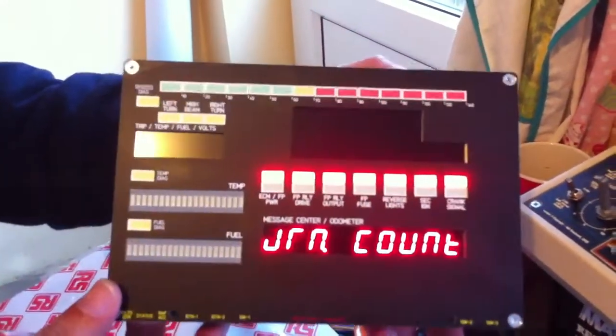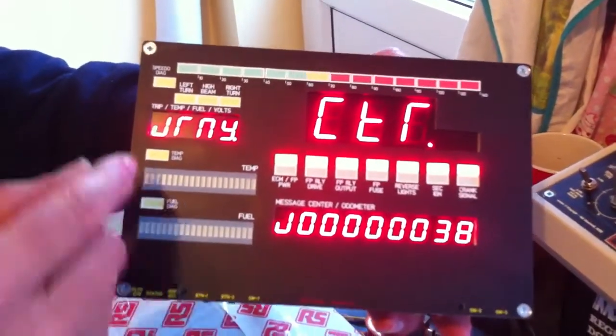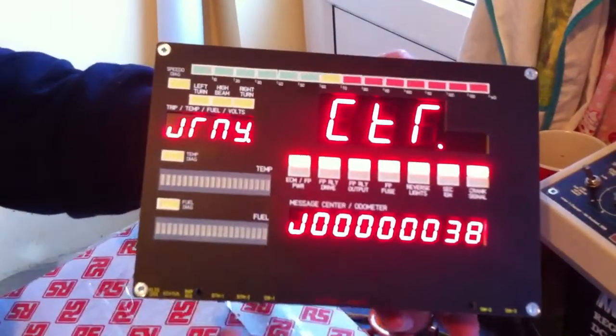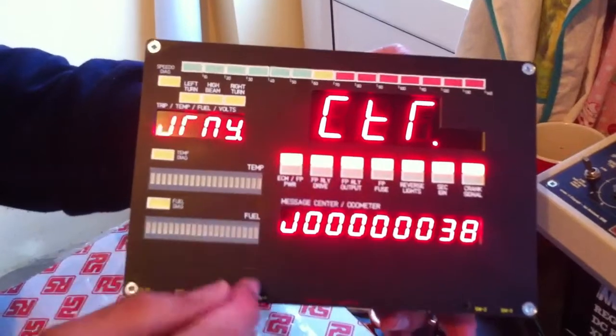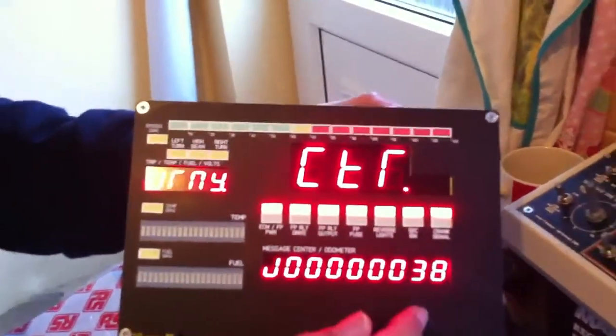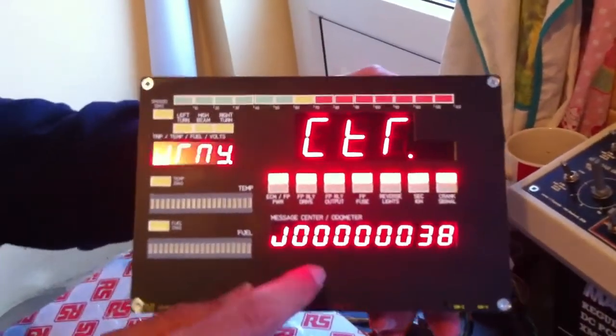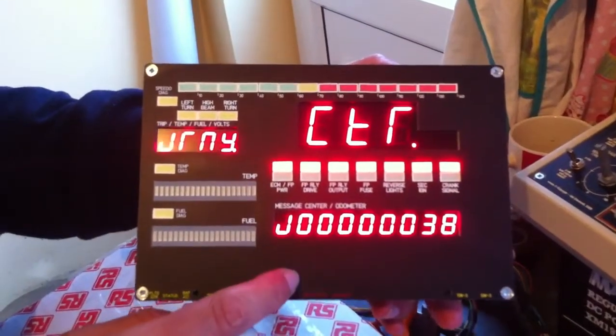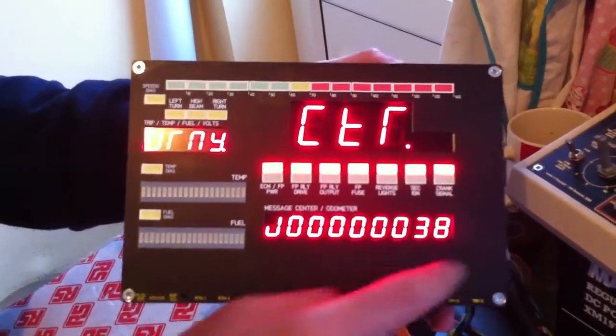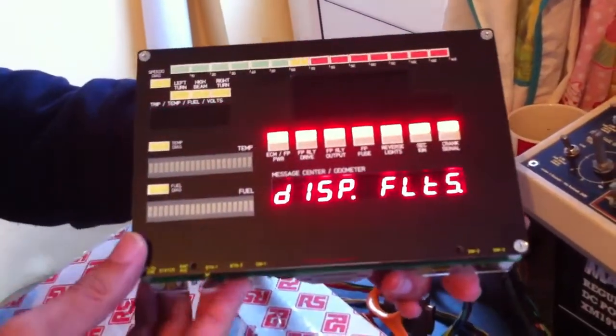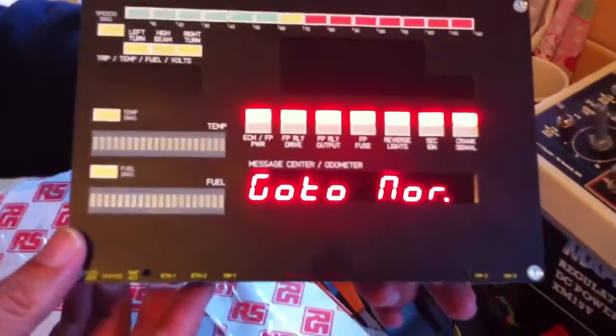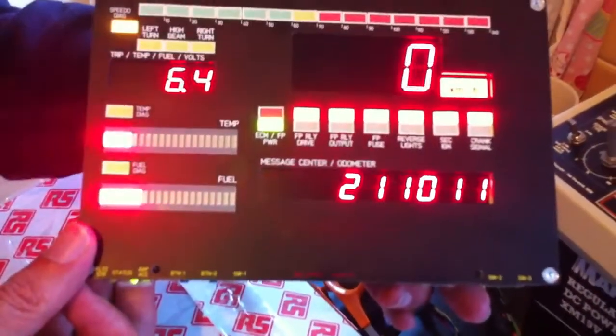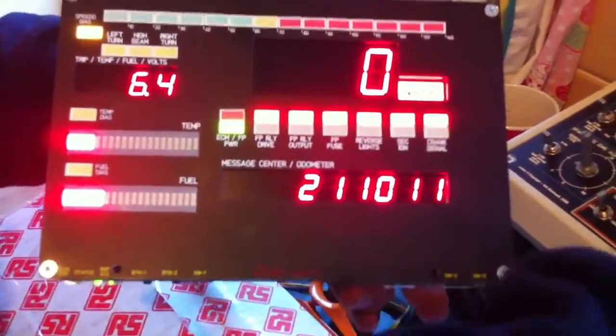If we push button number 2 when journey counter is displayed, this just shows journey counter to tell you what it is, and this J is short for journey, and that shows that we've had 38 journeys. That means that this unit has been powered up and powered down in normal running mode 38 times.